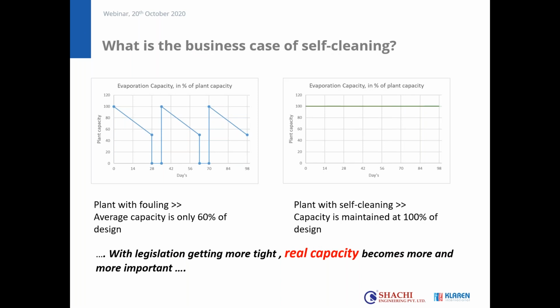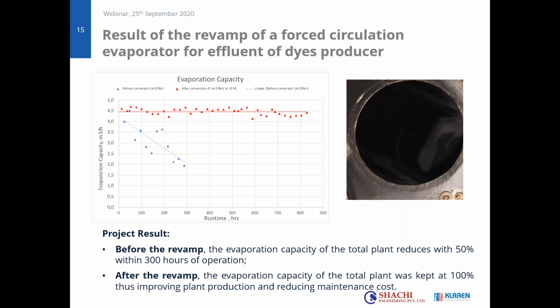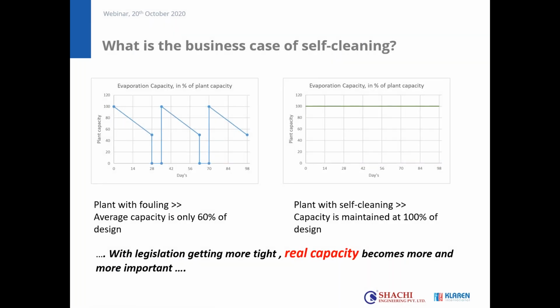So what I've just shown you in the picture here is the decrease in evaporation capacity versus a constant capacity. And in fact, that is the core of the business case. Because if you would look at a schematic picture, on the left, you would see that evaporation capacity goes down from 100% to 50%, and in this typical example, in 28 days, not to exaggerate it. After that, you would stop the plant, clean it, and when it's clean again, it would go back to 100% if you're lucky. In most cases, it will be less because there will be some fouling left, and the cycle will repeat itself. If you would then do the simple math, you would see that the average capacity of this plant is only 60% of the design.